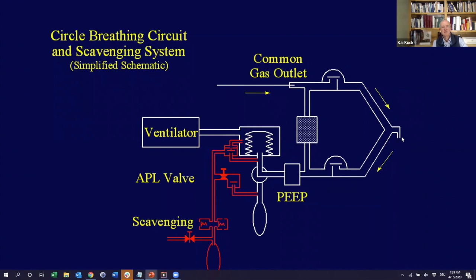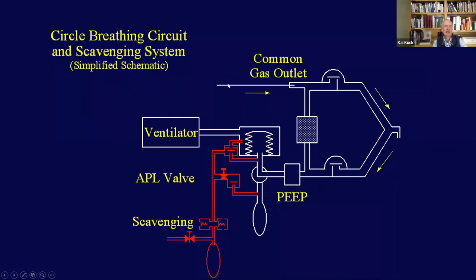So this is where the patient is connected, right? You have what's called here a common gas outlet. That's where fresh gas flow goes in, the mixture of air and oxygen, or even nitrous oxide if you need. There's also right here a vaporizer where anesthetic gas gets mixed in, and so that enters the breathing circuit. And then you have what they call a ventilator, and the ventilator pressurizes this box, if you will, and this box is then pressing down on the bellows.